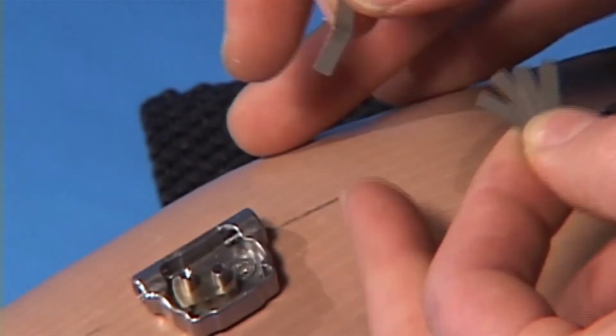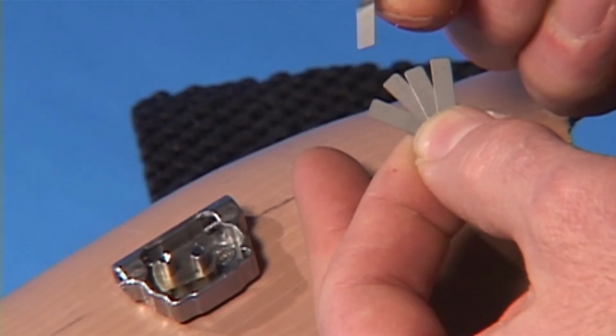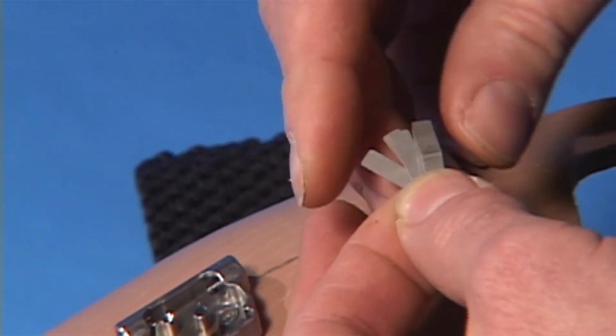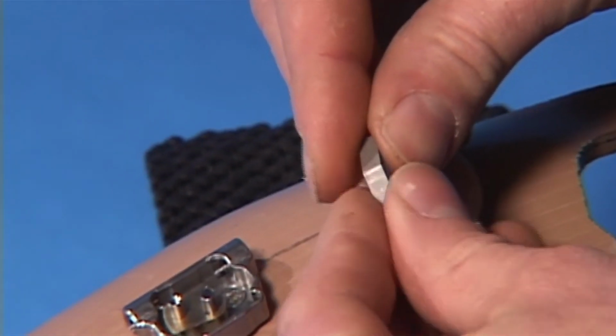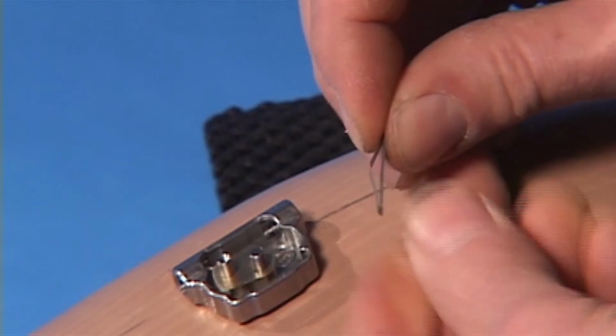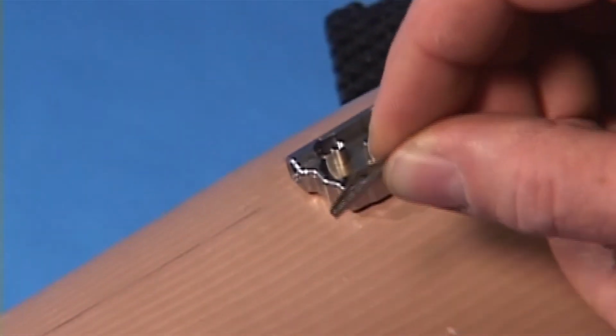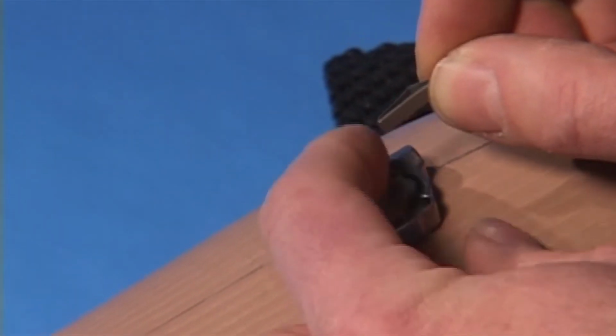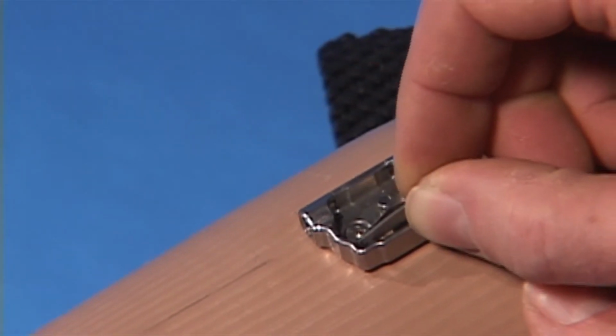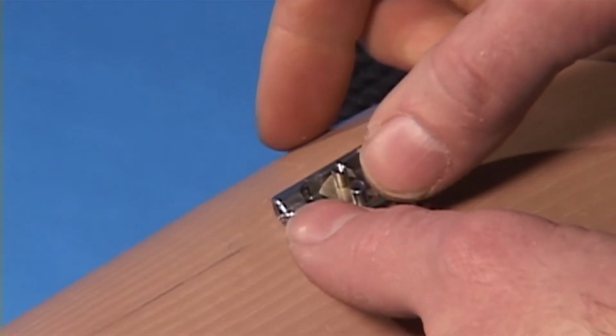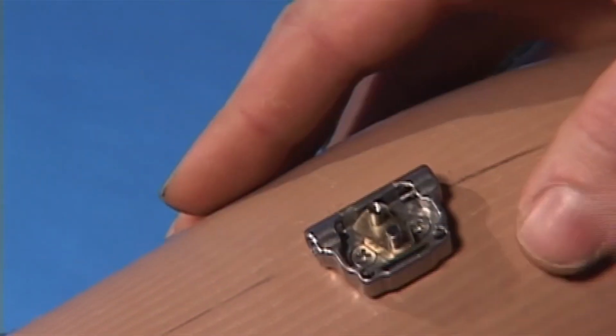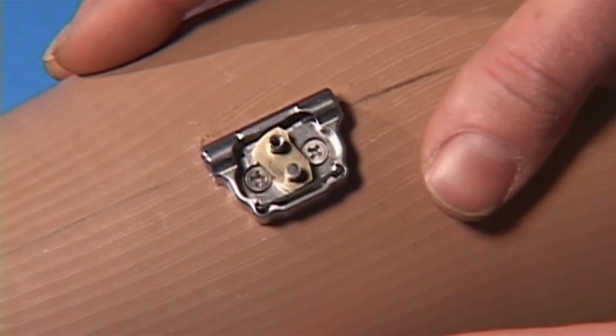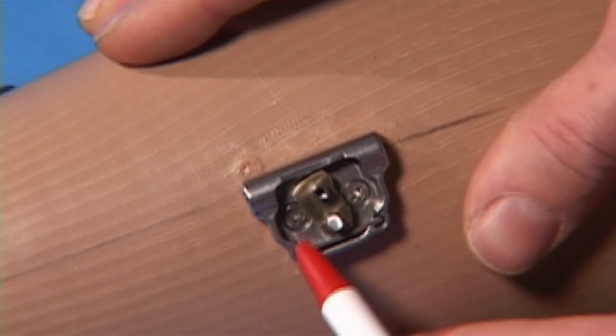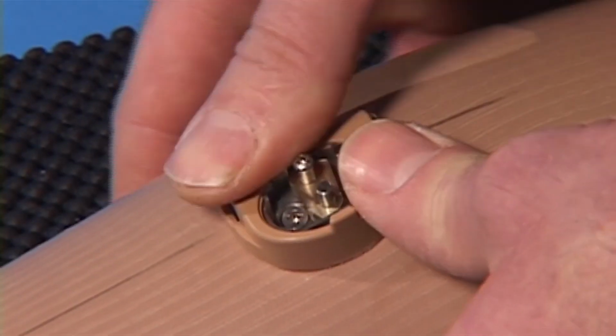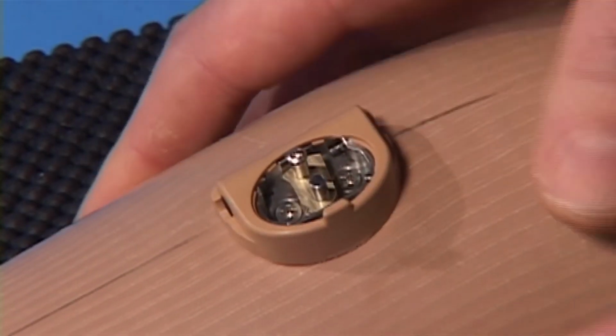Assemble the 5 leaf springs into a stack. Grasp them between your fingers or with a small pliers. The bent V-shaped spring should be located closest to the cam, with the vertex pointing toward the cam. Slide the stack of springs behind the cam, carefully forcing the spring stack ends into the recesses located on either side of the structural base next to the cam. Lightly lubricate the bent spring where it contacts the cam. Press the cover base over the structural base assembly.